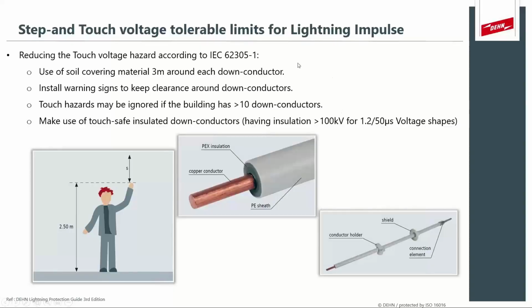If you're not able to achieve this, you can make use of touch-safe insulated down conductors. As I mentioned, it should have 100 kilovolts insulation for a 1.2 by 50 microsecond voltage wave shape. So that's also dependent on the rise time, to not overstress the cable. It's not 100 kilovolts at power frequency, but rather 100 kilovolts at 1.2 by 50 microseconds. This is an example of a special lightning insulated down conductor that can be used to ensure that our installation will be safe against touch voltages, ticking the first box of our lightning protection system and making sure that it's safe against lightning currents.